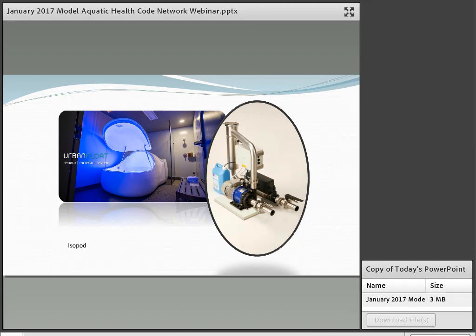There's the pump, and then the water comes in, then goes up that pipe into that big silver tall vessel. That's the filter. Again, that's not an NSF cartridge filter. It's basically a 1 micron sock that slips in there that is disposable. So when it starts getting clogged, you just replace the whole sock. Then it progresses from there to what looks like that lower line on the right. The black box on top, I'm pretty sure, is the heater. And if you look underneath that black box, it looks like there's another oversized mechanism. I'm reasonably sure that's UV.